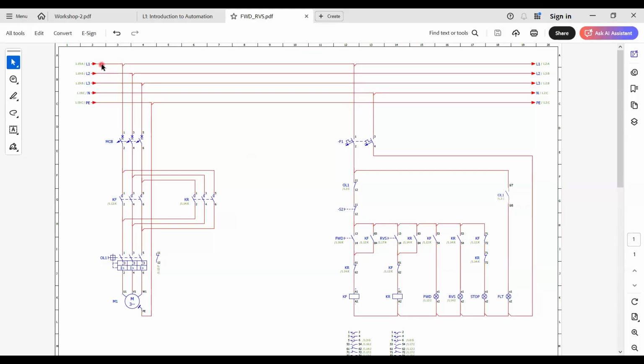So the three-phase supply L1, L2 and L3 comes to the main circuit breaker and it goes to the forward contactor. When the motor runs in the forward direction, the current will just pass through the forward contactor, then it goes to the overload relay. Then it is connected to the motor. So in the event of overload, this will trip this contactor and protect the motor from large current going through and protect the motor coils from overheating.